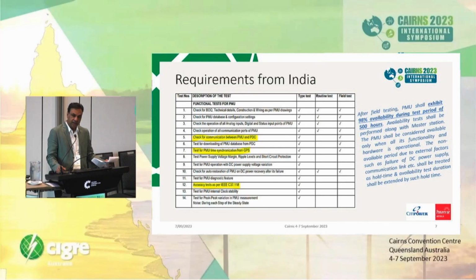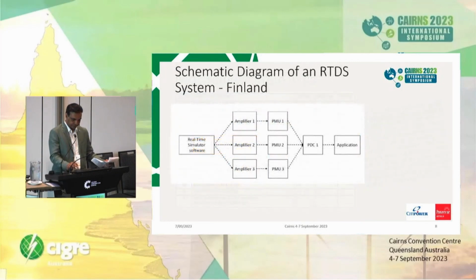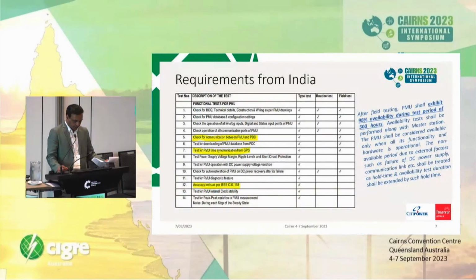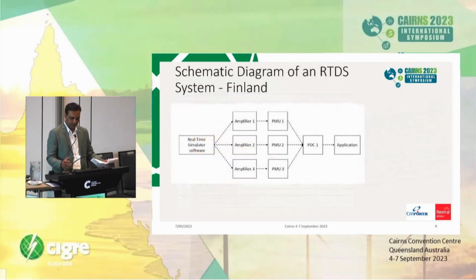By saying this, they have tried to ensure that everything, right from the CTVT to the control center, is tested. Also, points number 5 and 7, which I've highlighted: they have tried to ensure that the PMUs are communicating with the PDC and with the GPS. So these are methods adopted by the Indian utility to ensure that it's tested properly.